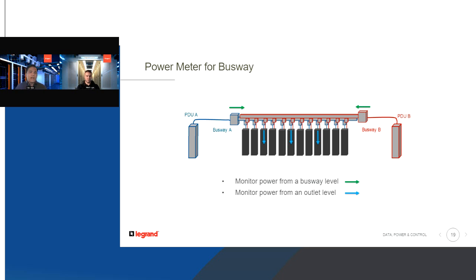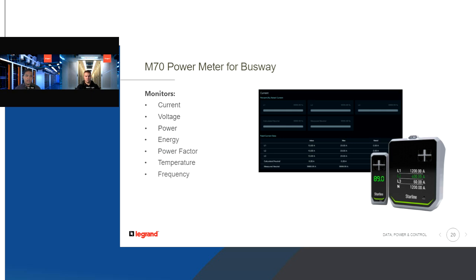The last product I'll show you, which we're using to address some of the AI influence on the busway, is monitoring. We can monitor both at the busway level and at the outlet level. For AI, we've seen interest in wanting to monitor and trend how much workload or current the rack is using. We can do that using a power meter in the plugin, monitoring that particular outlet. For end feeds, the outlet monitors current, voltage, and temperature, and it'll give you information like power, energy, power factor, and frequency.